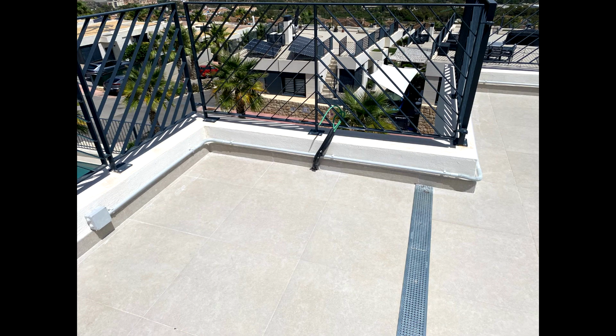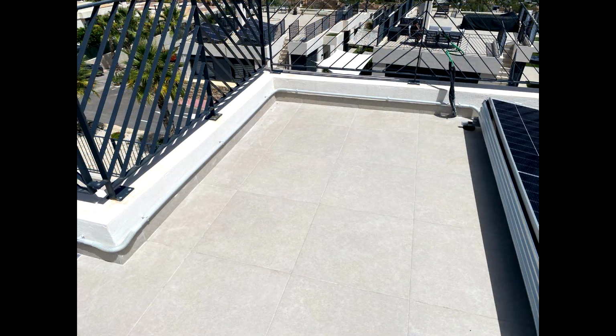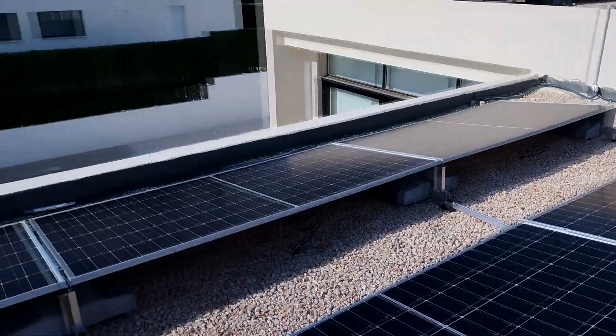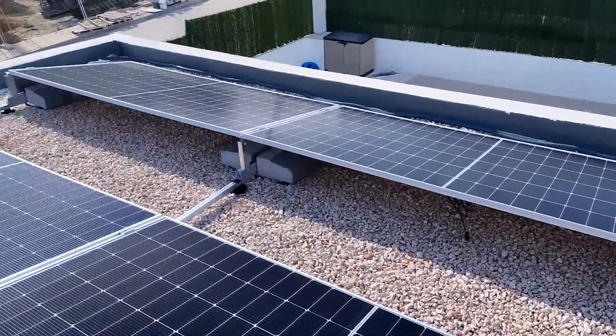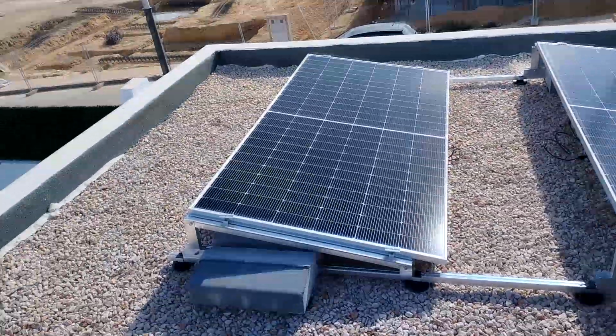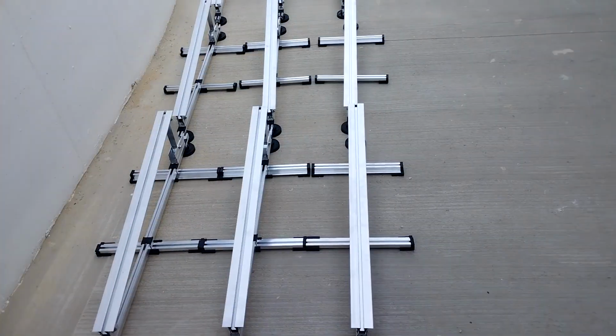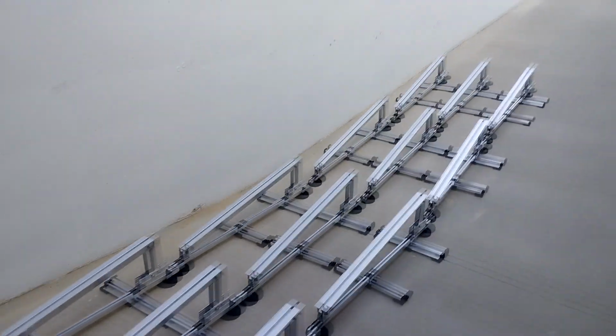Cables for the solar panels use insulation designed to withstand intense sunlight, so they can technically be installed directly on the roof. However, we never leave cables exposed on the surface. We always run them inside flexible or rigid conduits with good mechanical strength and UV resistance. This increases the lifetime of the installation and improves its appearance. We also bond all metal mounting structures to the building's earth connection, because saving money at the expense of safety is absolutely unacceptable. For mounting solar panels on different roof types, we use specially designed mounting structures.